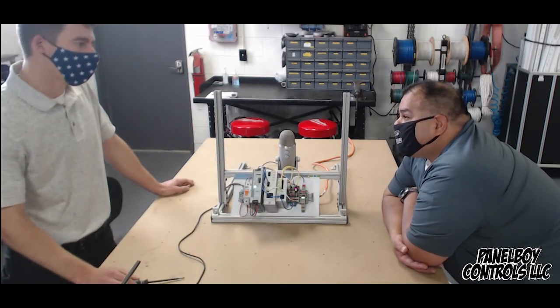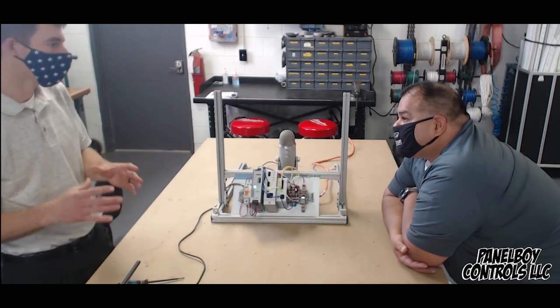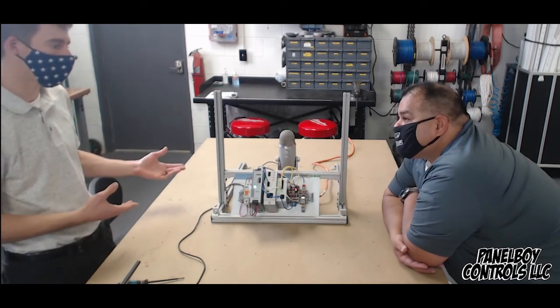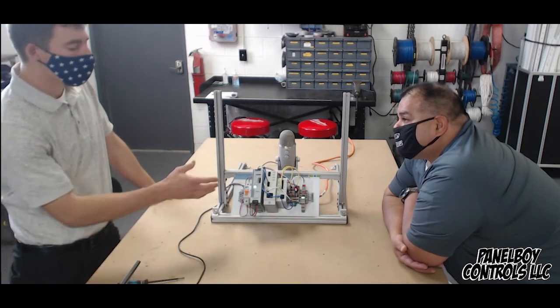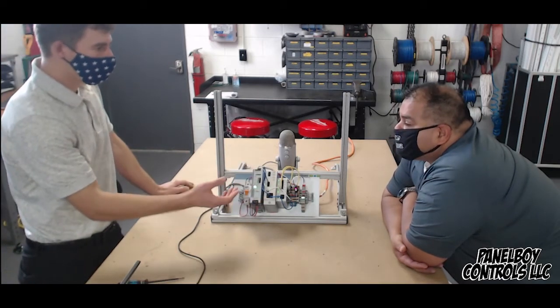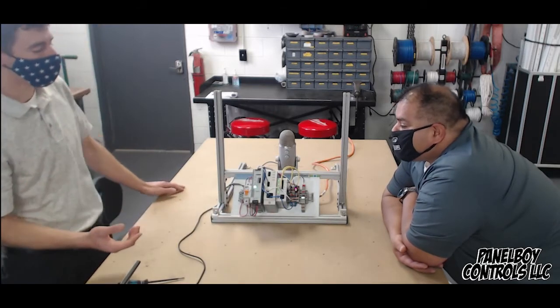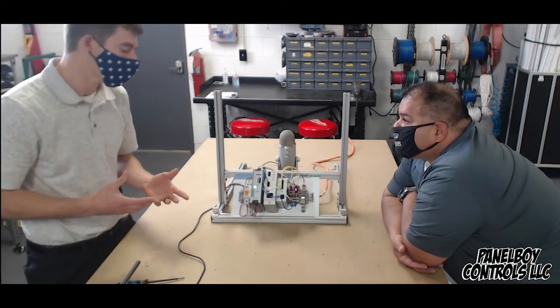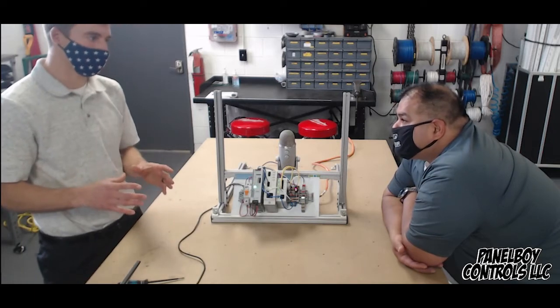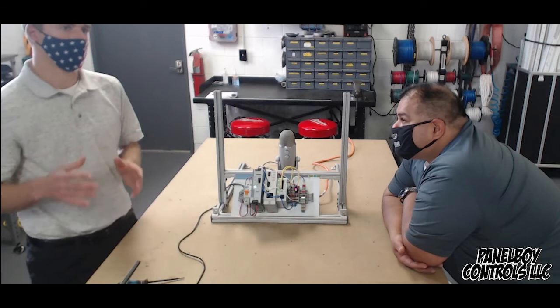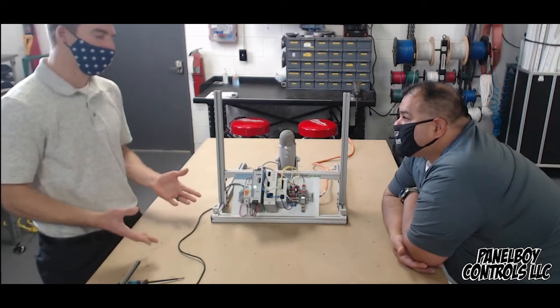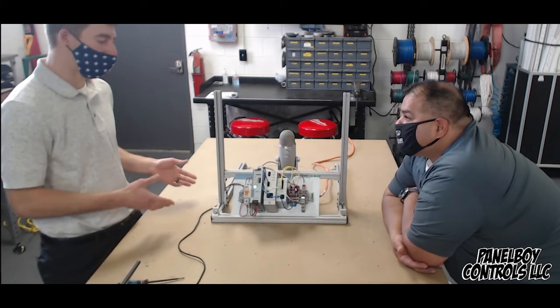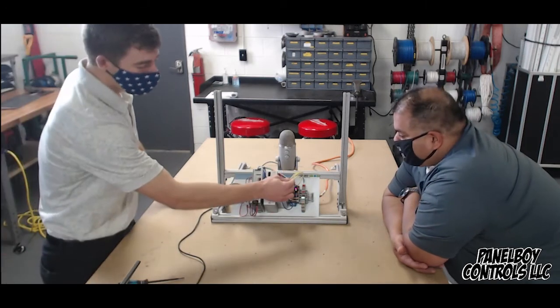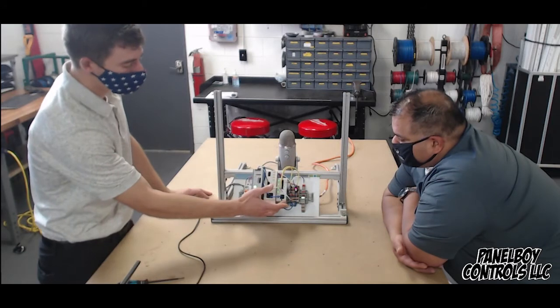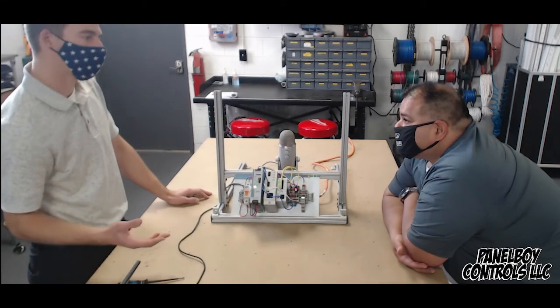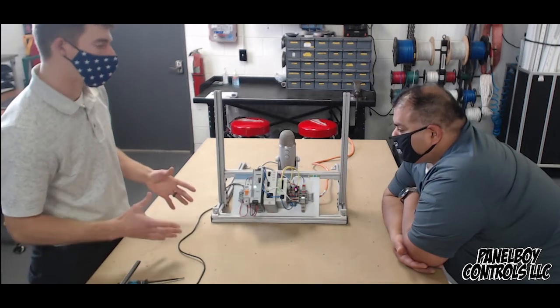Phoenix did come out with a standalone EtherNet/IP and PROFINET master module that would be wired back to your control scheme through Ethernet, so you can pull your tags that way back to your controller. Or if you use our remote I/O, we've got add-on modules that go right into our PROFINET and EtherNet/IP head stations, which again speak Ethernet back to your main controller. Yeah. So it would be just hardwired. We've got several components that are IO-Link that are meant to be IP20 inside the main control panel. That's why we came out with that standalone solution.